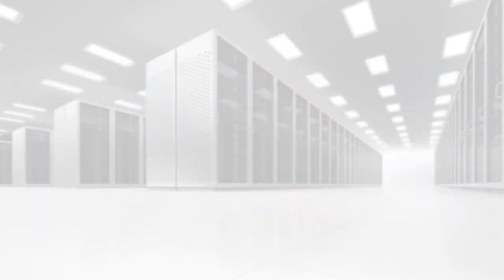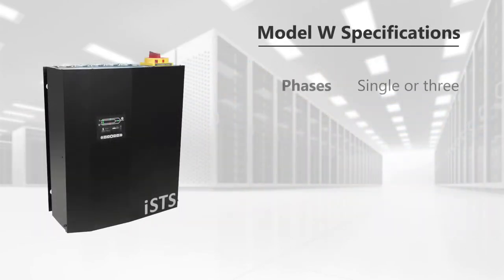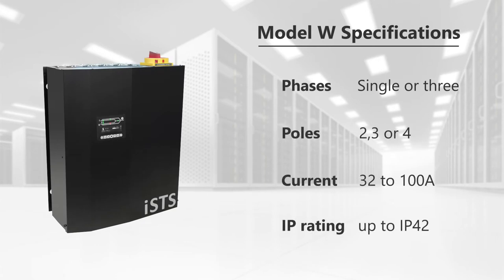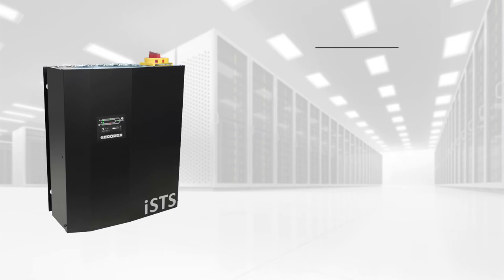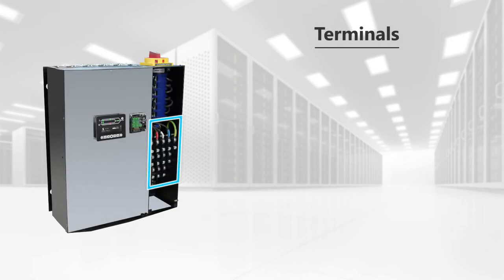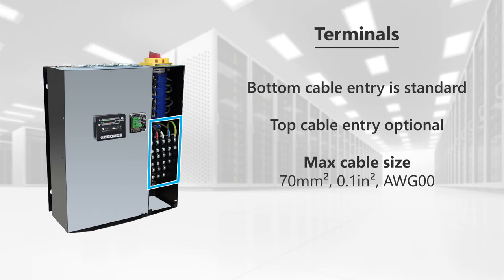This STS is suitable for either single or three-phase installations, with variants at 2, 3, or 4 pole. STS current capacity ranges from 32 to 100 amps. Ingress protection is rated up to IP42. Globally compatible with all region-specific frequencies and voltages.